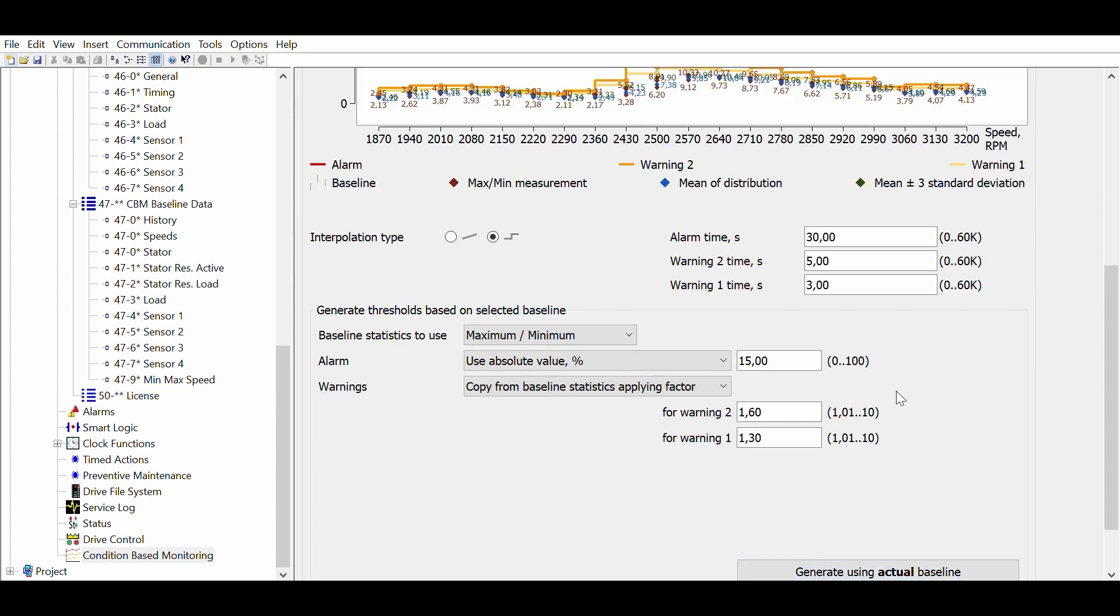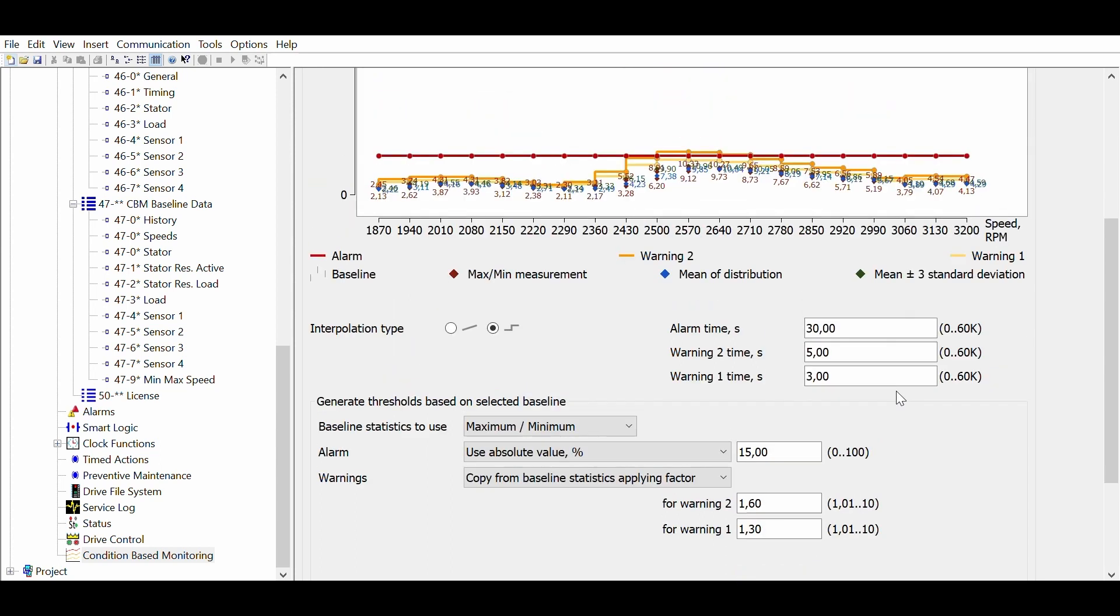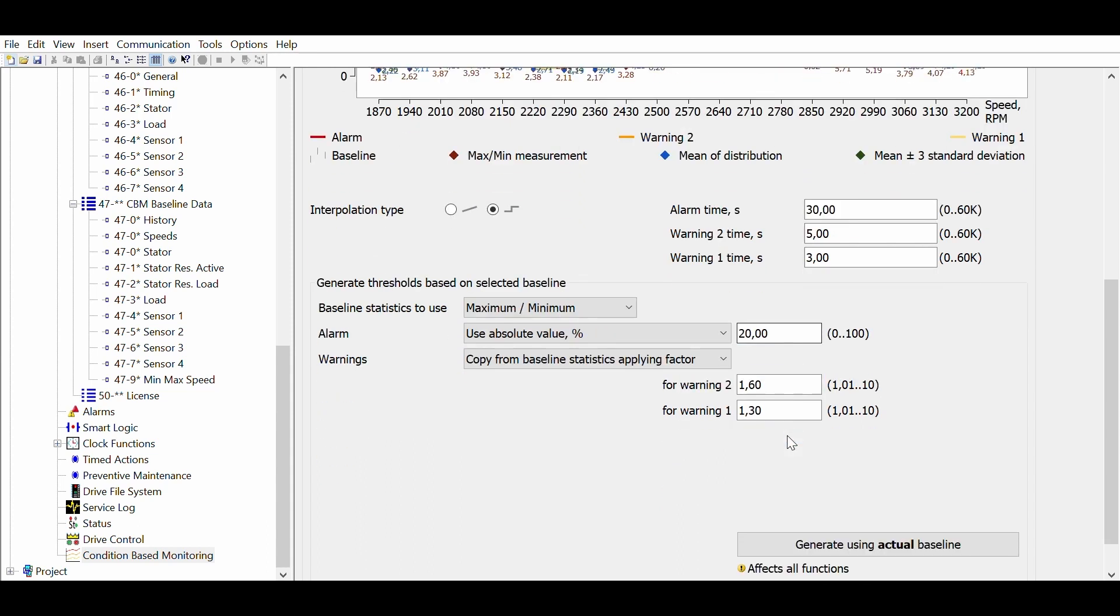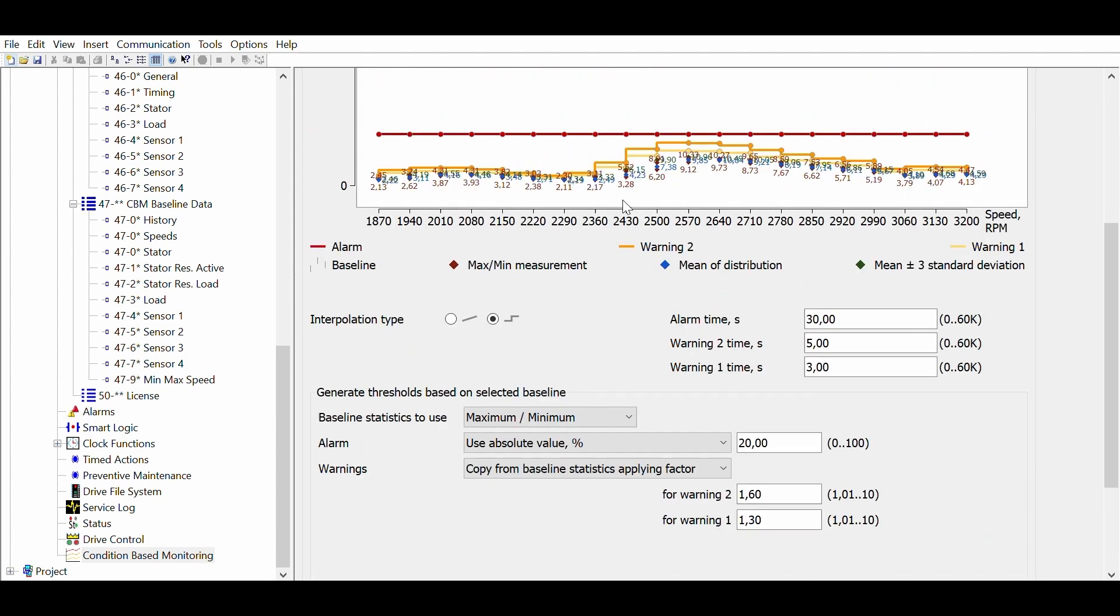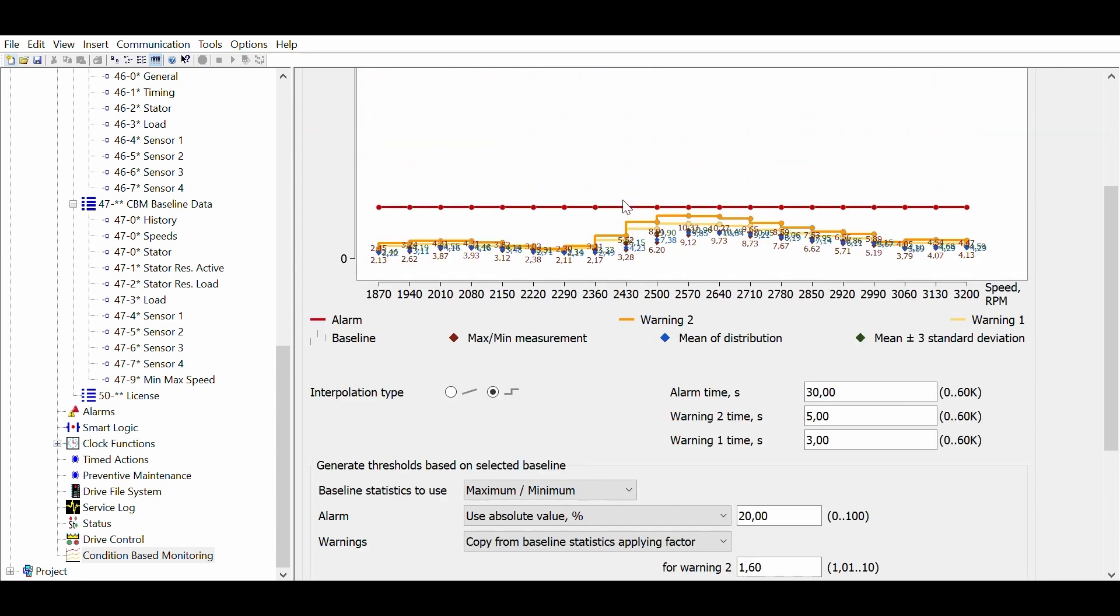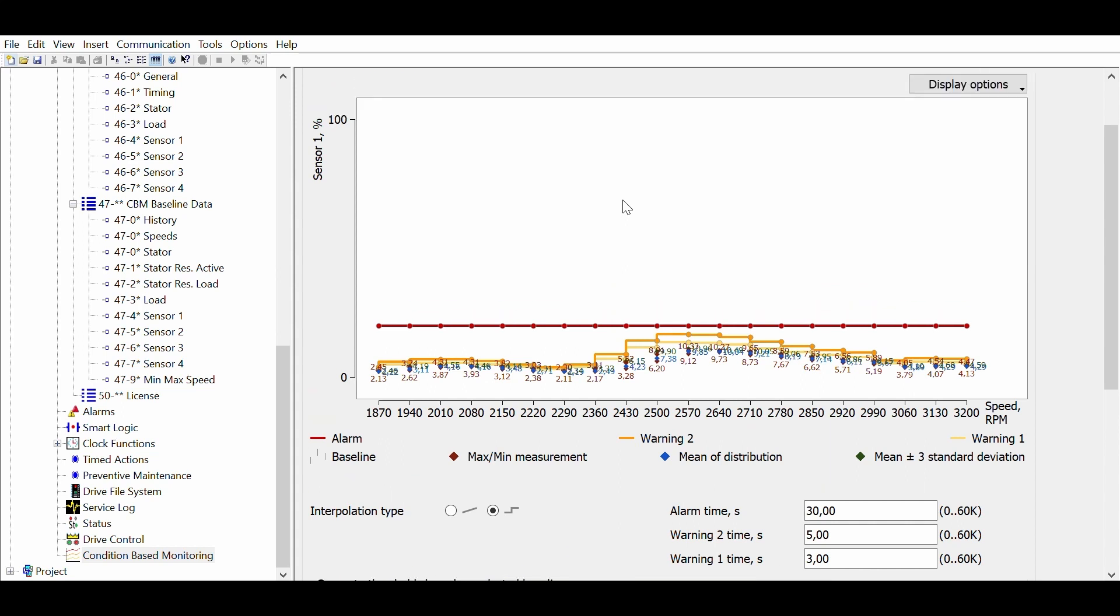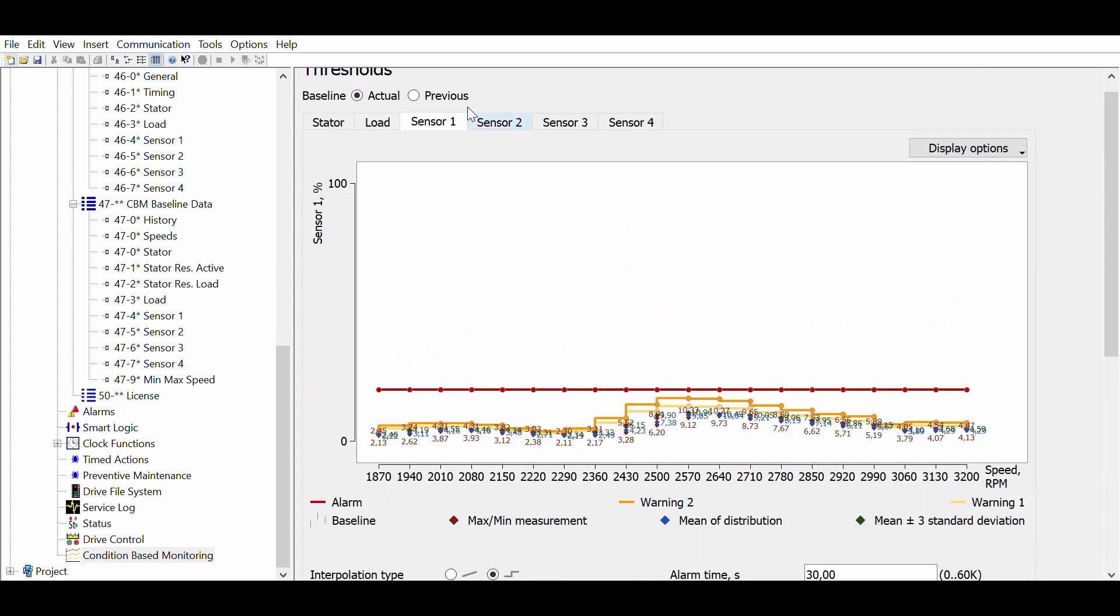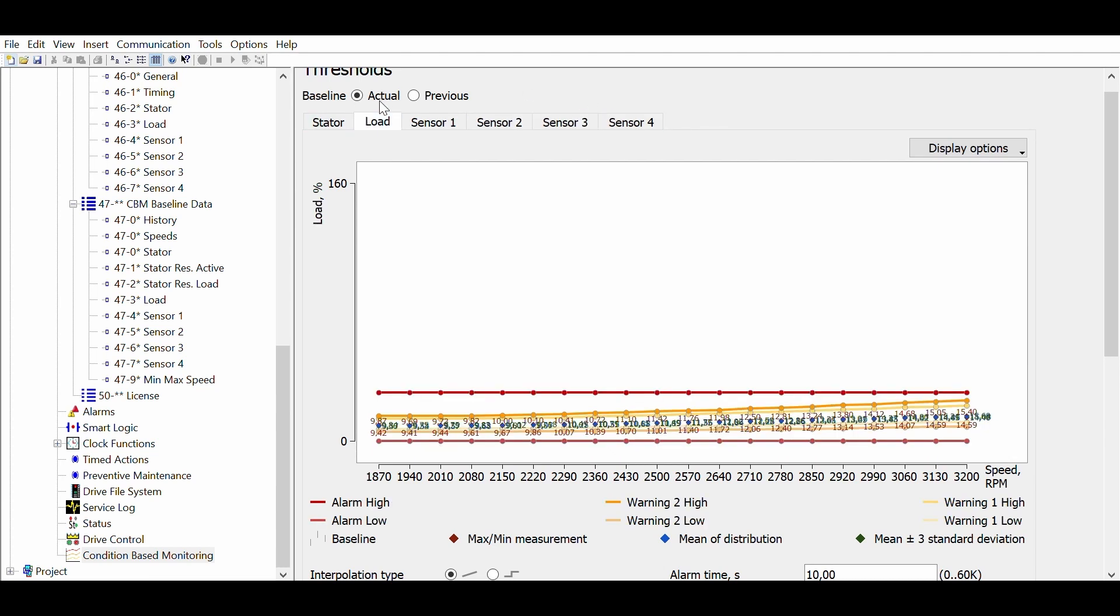You can generate the thresholds and check on the graph if everything is okay. In this case we can see that the alarm level is too low and we want to adjust that. We set the new alarm level to 20%, that is 20% of the vibration sensor range, which in our case is 25 mm per second. This means the alarm level is at 5 mm per second. Generate again, check, and everything seems to be okay. You are all set.